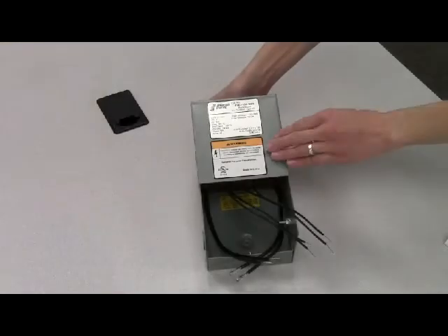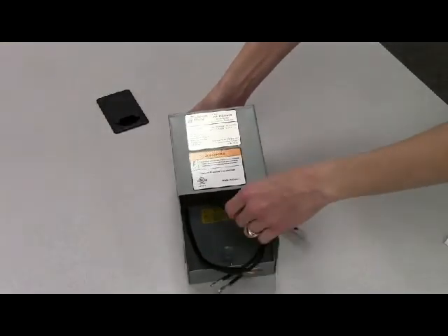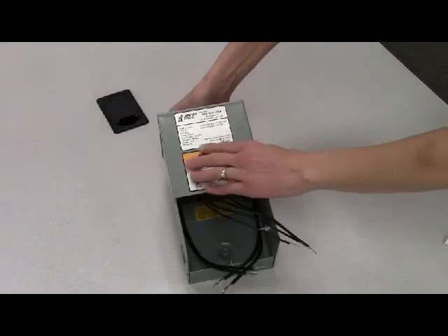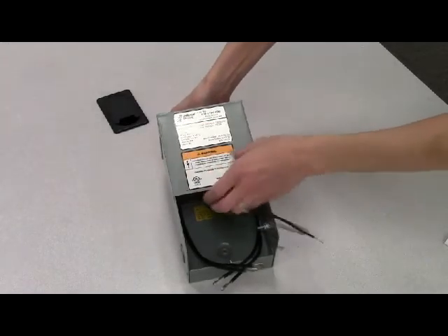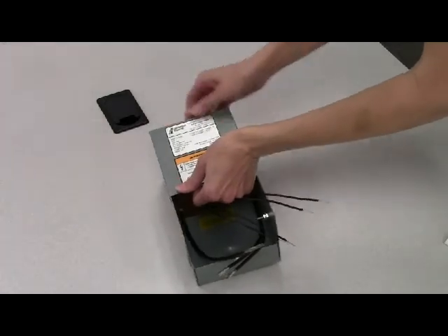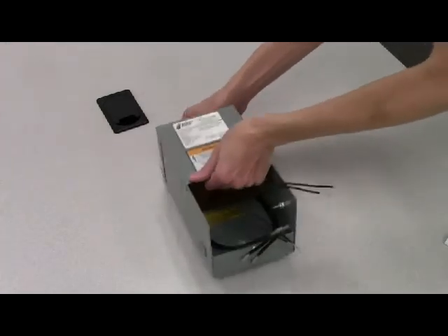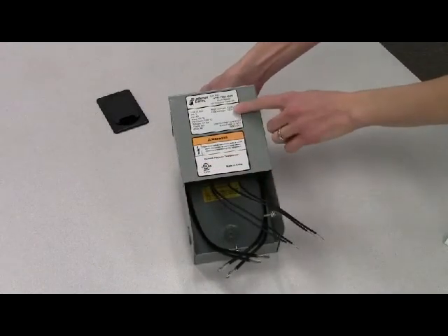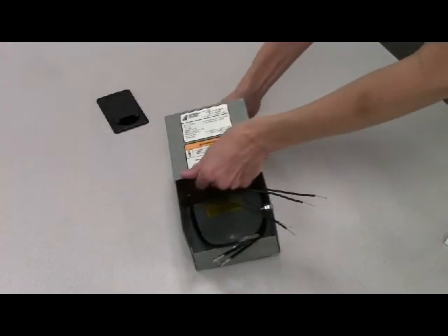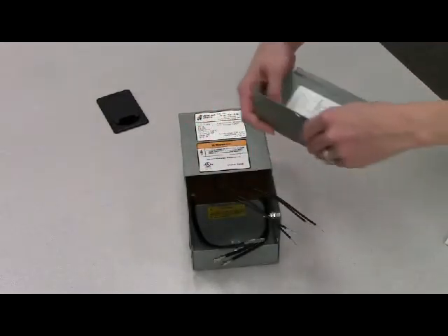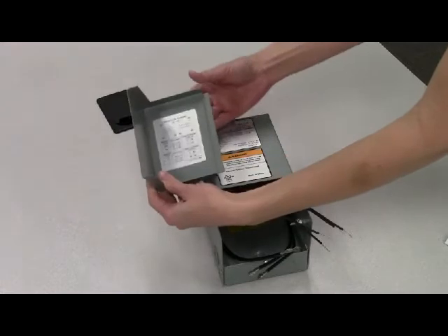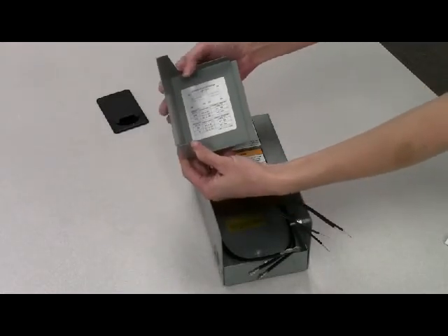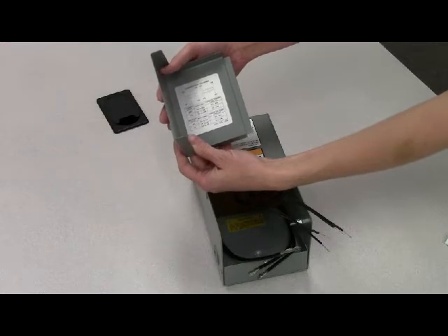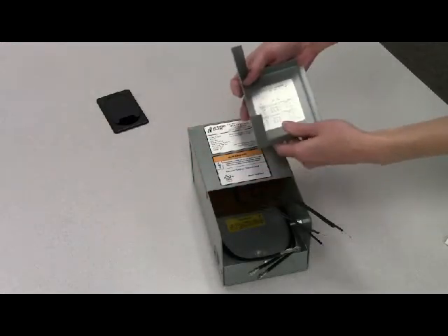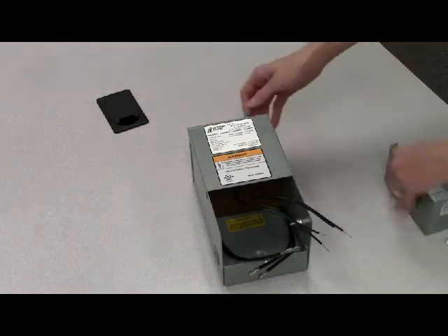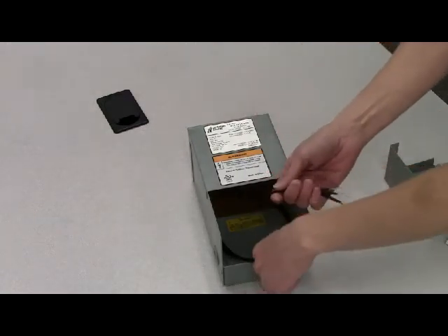So here we have a very common, simple, single-phase transformer, half a kVA, high voltage 120 by 240, low voltage 12 and 24. So we've got this 10-to-1 ratio here. So if we want to hook it up as a single-phase dual voltage transformer, here's our easy connection diagram right here with our nice H's and X's. However, the potential for this transformer is not limited to that. First of all, let me show you a couple of things.